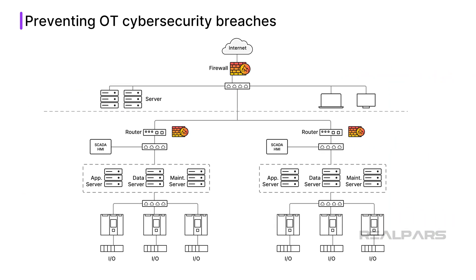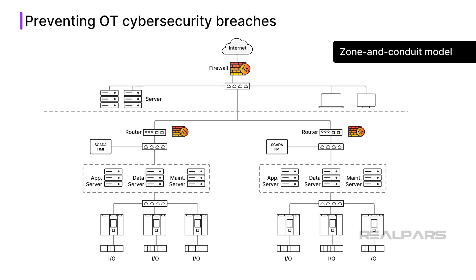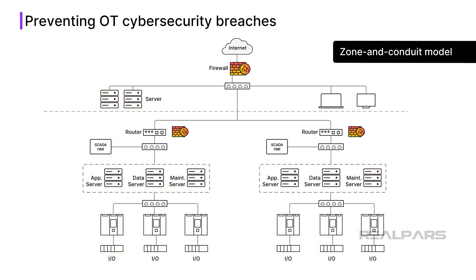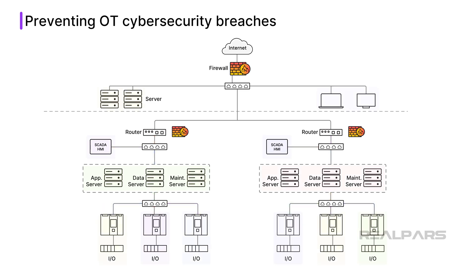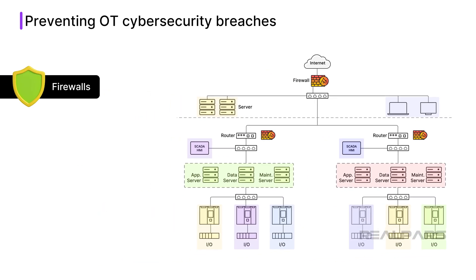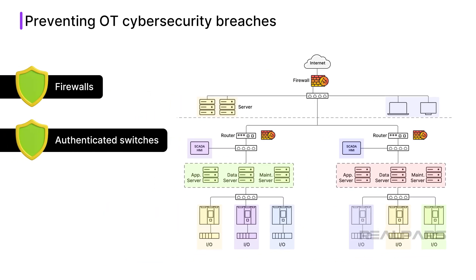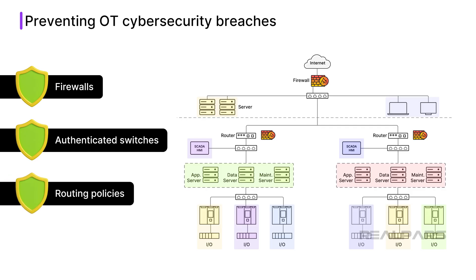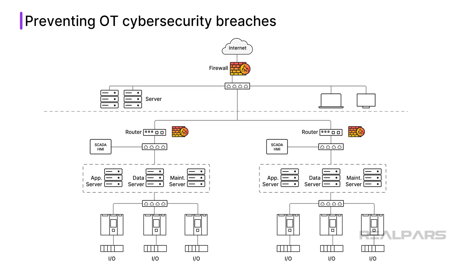Then, design your system architecture using the Zone and Conduit model. This strategy separates the network into zones with similar security requirements — for example, PLCs, SCADA, and servers — and defines secure communication paths or conduits between them. Appropriate protections such as firewalls, authenticated switches, and routing policies are applied at zone boundaries.